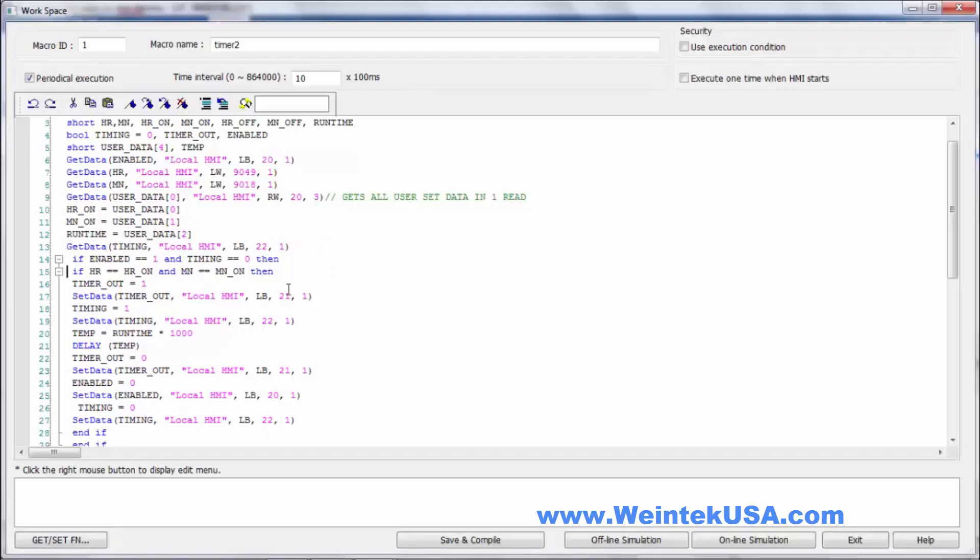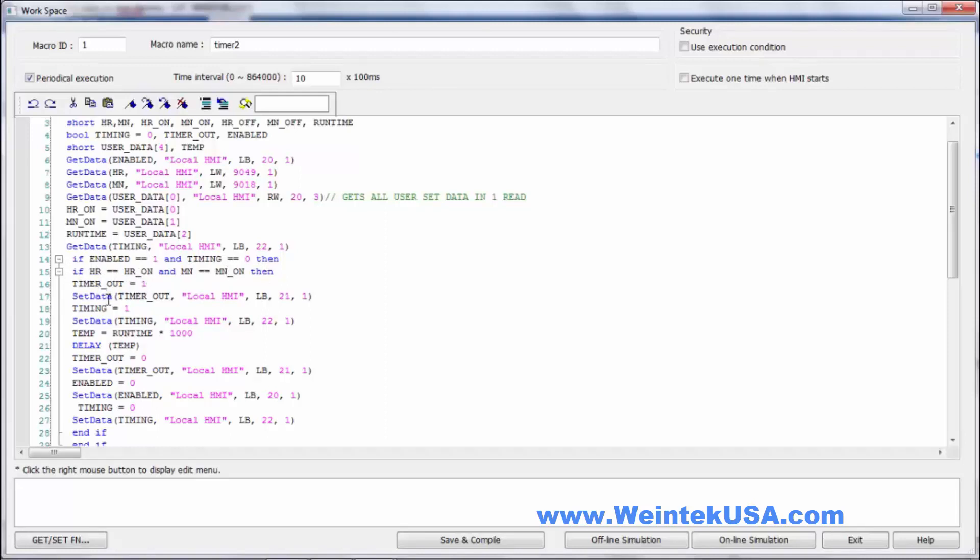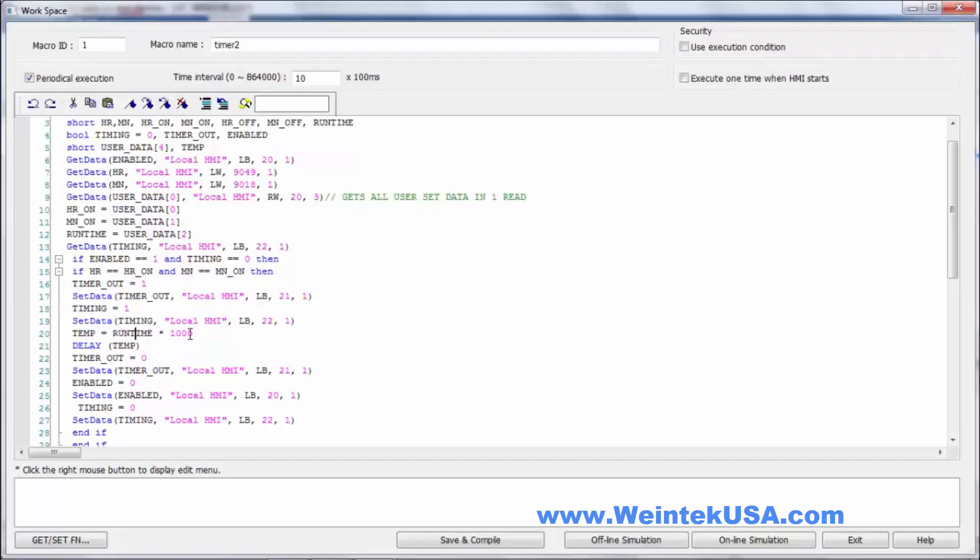And so we don't keep turning it on every second. So what we do here, that normally the state of that would be zero. If we're enabled and we are timing, we compare the hour to our hour set point and the minute to our minute set point. If both of those equal up, we will put a 1 in timer out and set that value to our output bit LB21. We'll put a 1 in timing and write that to our timing bit LB22. We're gonna take our temp value, which at this point is null. We're gonna take our run time set point and multiply it times a thousand, turning it into milliseconds. We're gonna do a delay for that number of milliseconds.